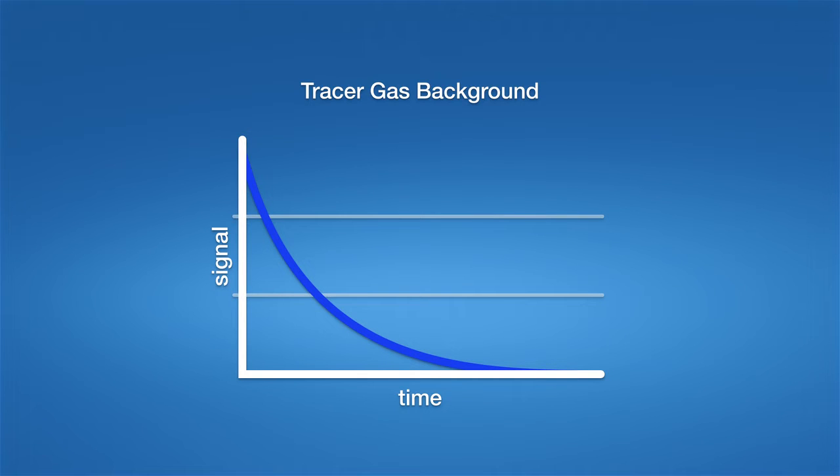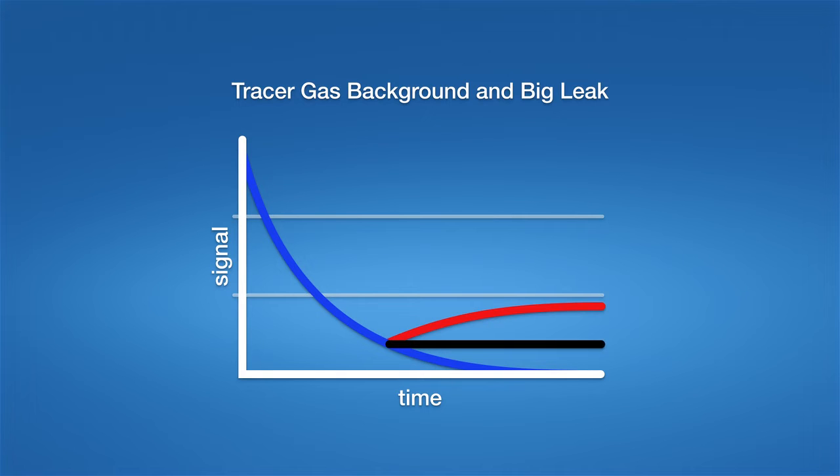Let's assume our test object inside the vacuum chamber has a rather big leak. After applying tracer gas to the test object, the red curve will be shown instead of the blue curve. In order to only see the red curve of the leak and not the blue curve of the natural background, we press zero before applying tracer gas to the test object.